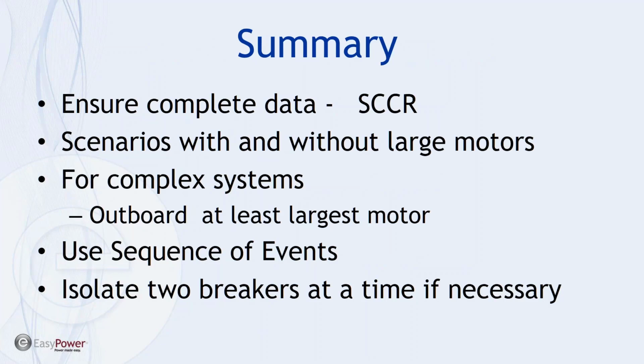So in summary, what we've tried to highlight is how important it is to have complete data when we're setting up motor control centers, whether they're discrete or in the form of an icon. IEEE recommends that we compare scenarios with and without large motors. In this case, they're talking about anything over 50 horsepower.